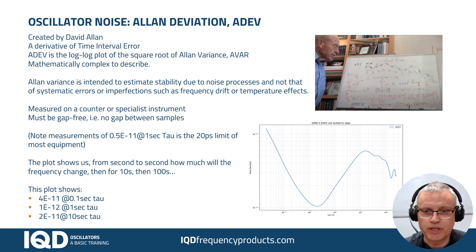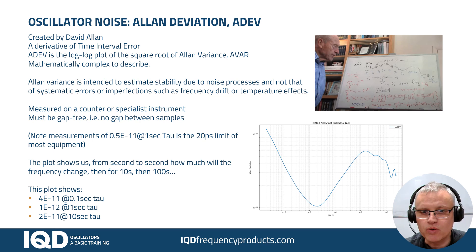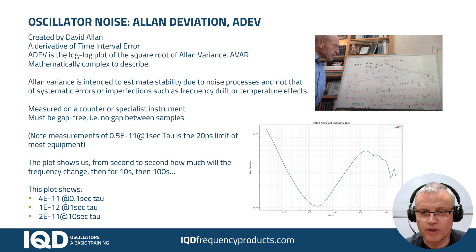If you're using an older counter, just be aware of that. One other thing we would say from experience is that a lot of counters have a noise floor of 20 picoseconds, which equates to 0.5×10⁻¹¹ at one second tau on an Allan Deviation plot. So if you're looking at an Allan Deviation plot and you notice that at one second tau it has a figure of 0.5×10⁻¹¹, there's a fairly reasonable chance that that's caused by the instrument rather than the oscillator, and the oscillator is in fact better than that.